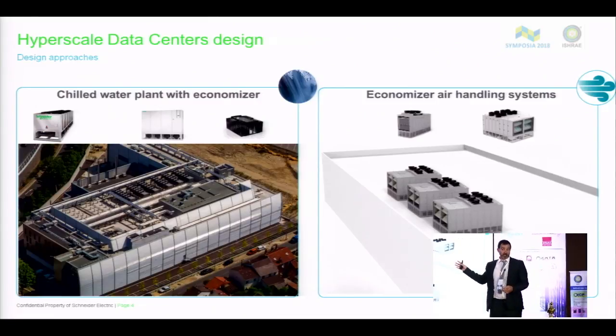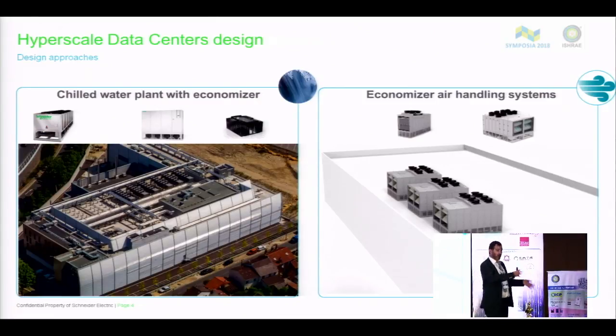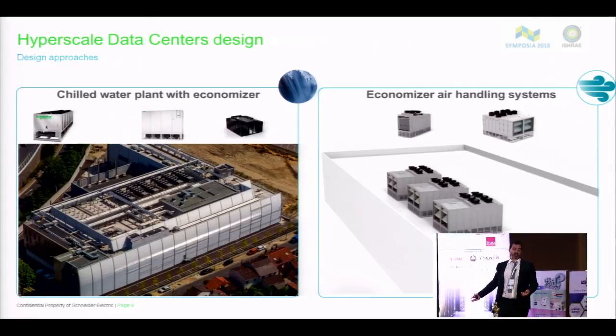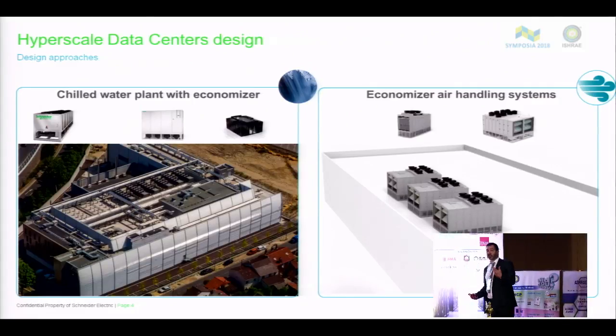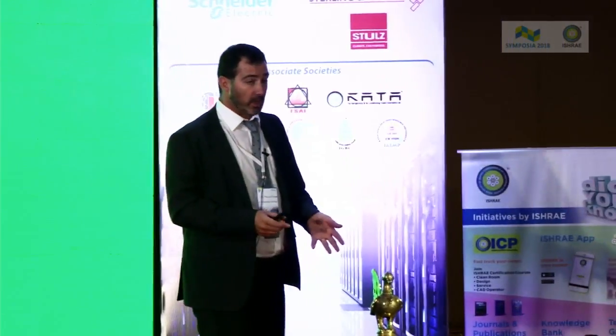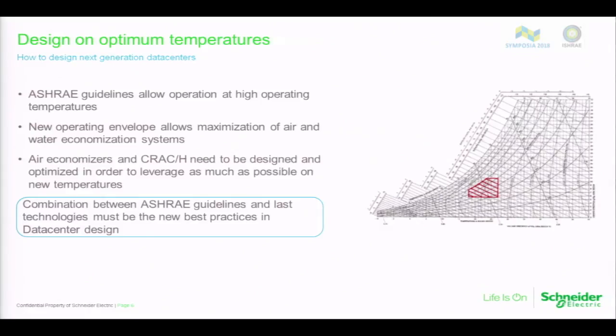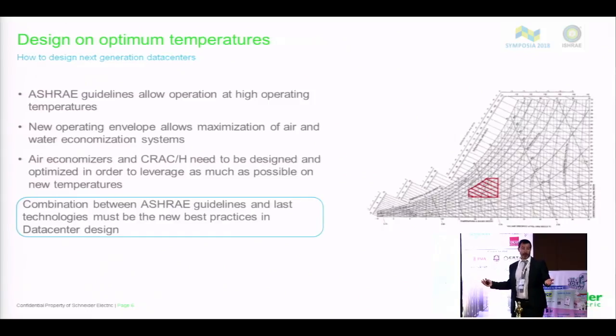This is not to say that the DX systems, the direct expansion systems, are wrong, but in large and extra large data centers they are less efficient or optimized than these two systems. For sure, looking at these two systems, the first question is what design temperature we should consider. Starting from the latest ASHRAE regulation and recommendations, looking at the recommendations of the rack producer and the manufacturer, and what the challenges are for the colocator.